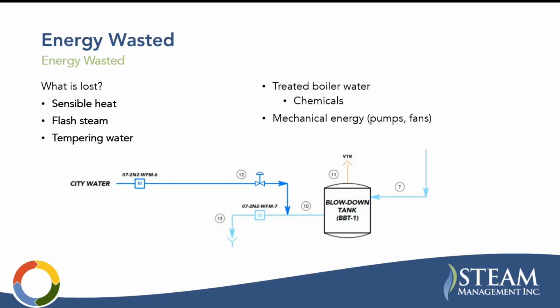And then tempering water. So I want to show this diagram again because in your bottom blowdown tank, typically you're at atmospheric pressure and you're going to be discharging liquid at 212 degrees. While most facilities have a sewer limit of 140 degrees is typical. And so you will commonly see a tempering valve on these bottom blowdown tanks. And you're basically just spending city water to cool that off just to get it below sewer temperature limits. So you don't damage your drainage system. So that is a significant amount of waste.